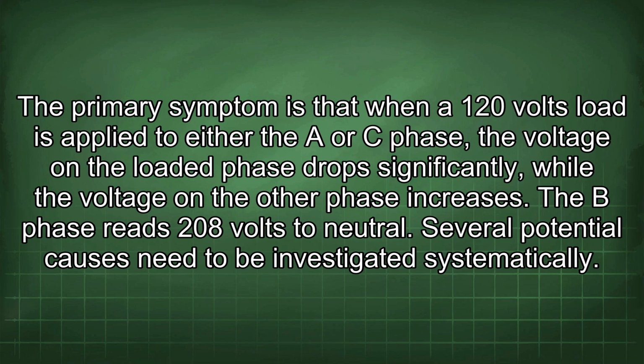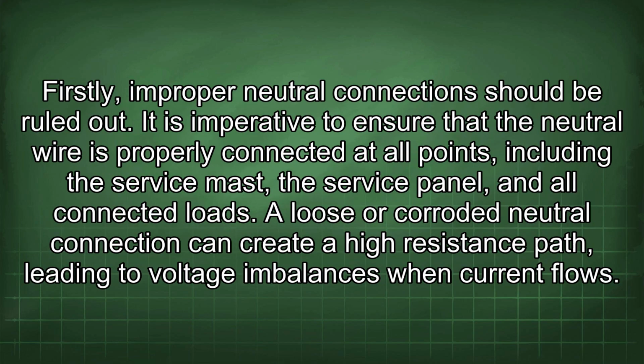Several potential causes need to be investigated systematically. Firstly, improper neutral connection should be ruled out. It is imperative to ensure that the neutral wire is properly connected at all points, including the service mast, the service panel, and all connected loads. A loose or corroded neutral connection can create a high resistance path, leading to voltage imbalances when current flows.